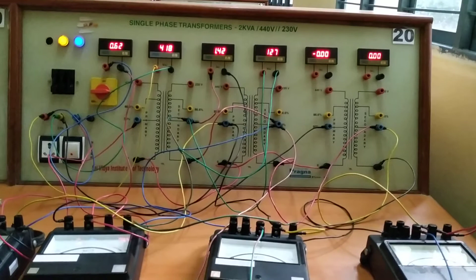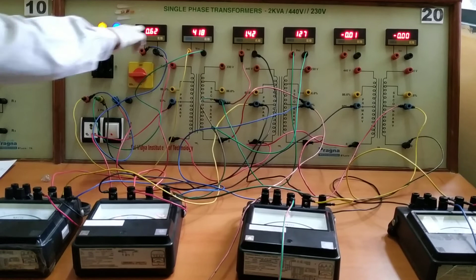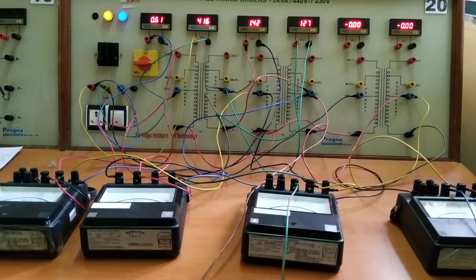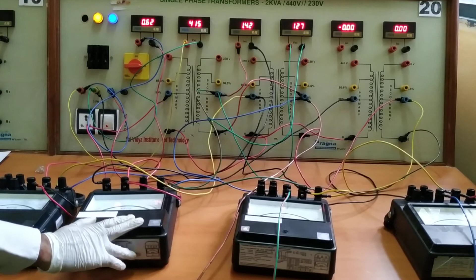For the loading of 2 amperes, again we note down V1, I1, V2, I2, W1, W2, W3 and W4. V1 is 416, it's fluctuating. I1 we can consider as 0.62 amperes. V2 is 127 volts, I2 is 1.42 amperes. Already in the instruction class you know how to take the wattmeter reading without parallax error, and how to calculate the wattmeter constant. Directly checking the reading: W1 is 40 watts, W2 is 250 watts, W3 is 40 watts, and W4 is 100 watts.